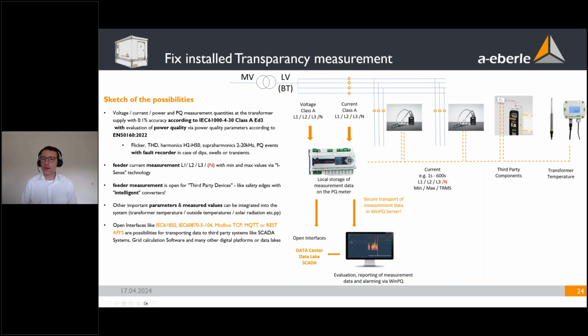It has to be open not only on this side but also on the OT technology side, in case of data communication, and therefore we provide several open protocols and interfaces like 61850, 104 -- more of a European protocol -- Modbus TCP, which is used worldwide, a new protocol called MQTT, or also a new web server API, REST API. If you have questions regarding protocols, standardizations, and opportunities, please come back and ask us. We will answer all these questions.